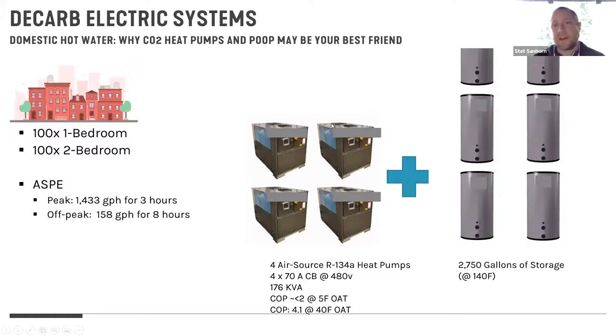And so I just want to point out that when it's cold outside, even with storage, for four of these units, when I calculate it out, I get a connected load of 176 kVA. And that is really important because that can be the difference between a transformer that fits in a vault outside below grade and having to come above grade, at least in our urban context.